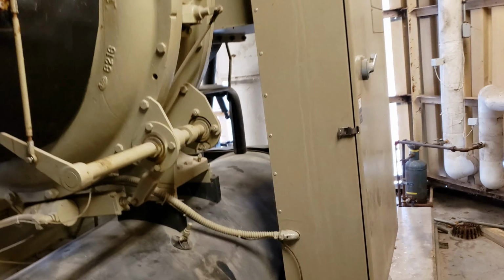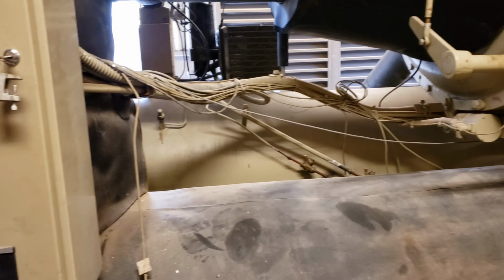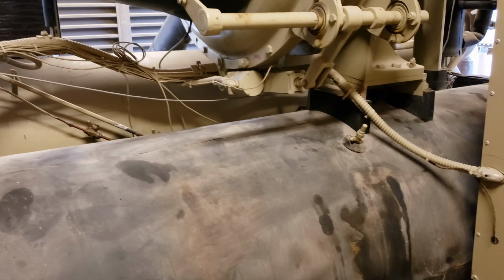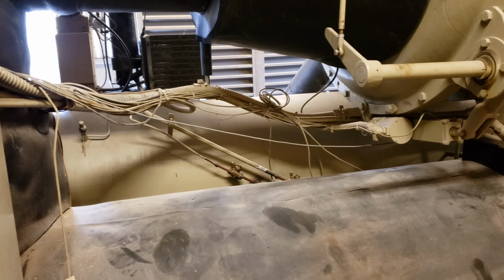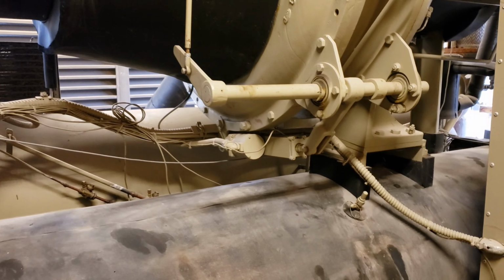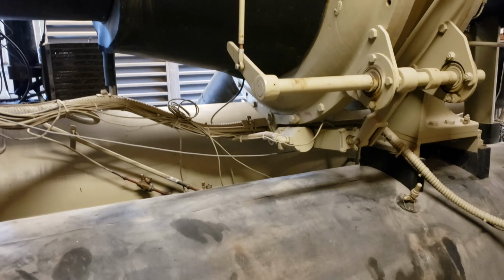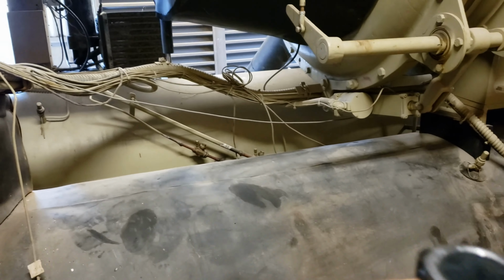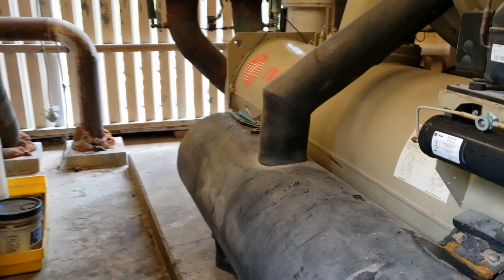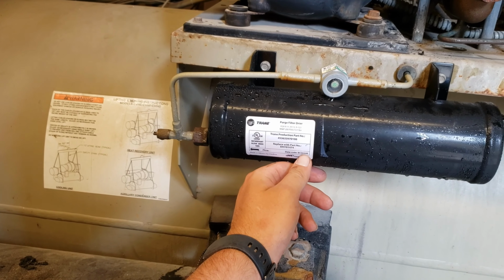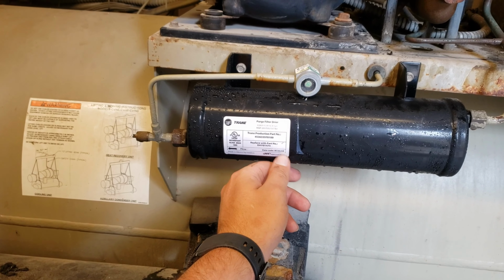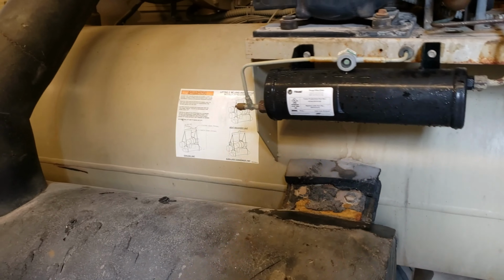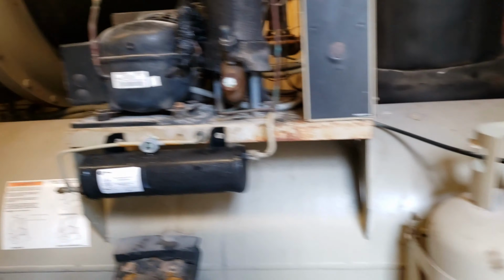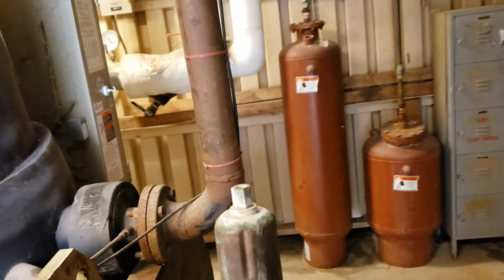So this is what I'm talking about, folks, what I'm trying to educate people about. This piece of equipment here, before we got here, was basically nothing more than scrap metal. It had a starter coil going out, purge issues out the wazoo, oil issues, sensors, all kinds of stuff. It had not had very good maintenance. Heck, the purge filter that it had sitting on the purge had a factory date code of 2014 — you can see right there, this is June of 2020.